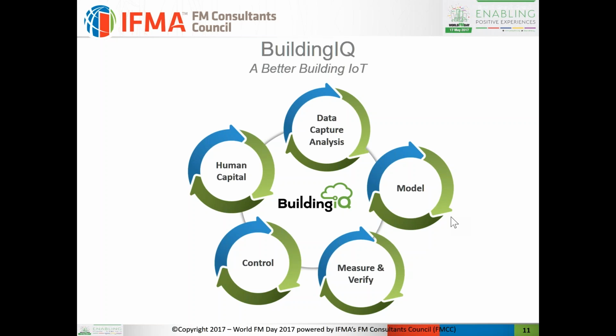In many senses, when you're talking about an IoT infrastructure or a digital twin, if you will, of a building, you want to create a model using mathematics to understand what the building does. In the context of energy management and HVAC systems, you're really thinking of a building as a big old heat sink. How quickly does it gain heat? How quickly does it lose heat? Where does it lose heat quicker than other places, and where does it retain heat differently based on time of day and so forth? So one model that's created is called a thermal model of the building, and that model has to do with the temperature, the historical temperature, the historical energy consumption, the historical BMS performance, occupancy schedules, and occupancy patterns. All of those feed into a baseline model, or base model, of the building.